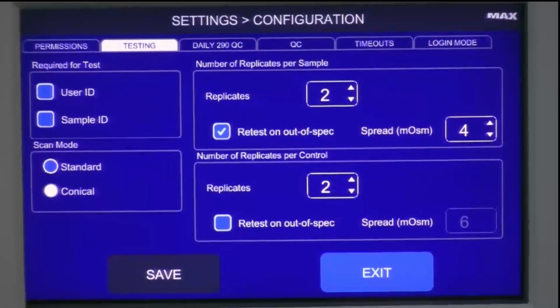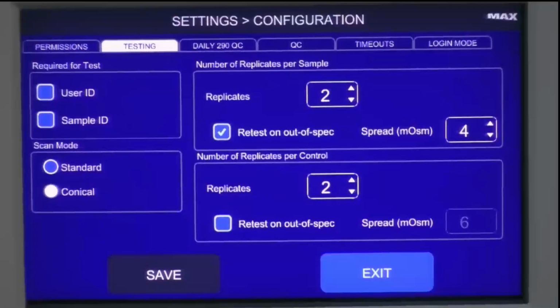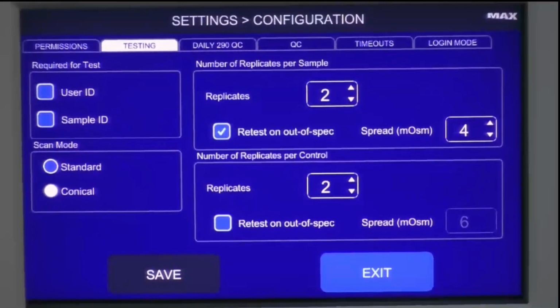If you're a laboratory who's performing duplicate testing on all of your osmolality tests right now, let's say you're doing it on an Osmo 1, where you have to run each sample manually 2 times, standing in front of the instrument to run both tests. Or let's say you're doing it on the Osmo Pro, where you have to pipette into 2 cups samples from the same sample tube each time so that you can ensure you're running duplicate results. Those days are over. So you just put your primary sample tube on the instrument. Here on this menu, you're going to let the instrument know, I want to run replicates on every sample. So 2 tests for every single sample.